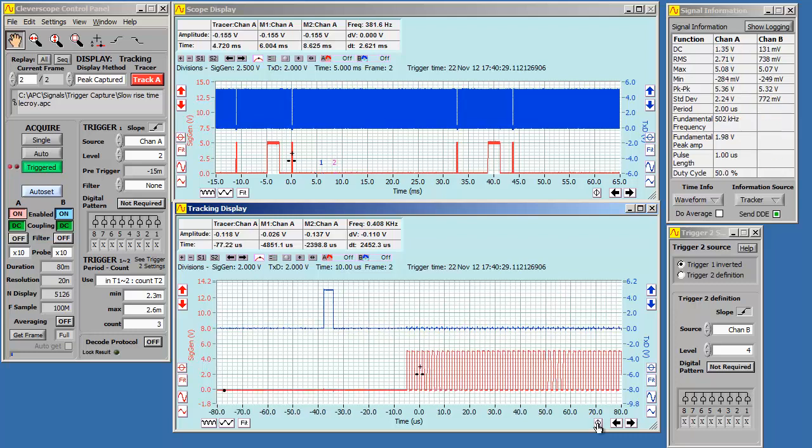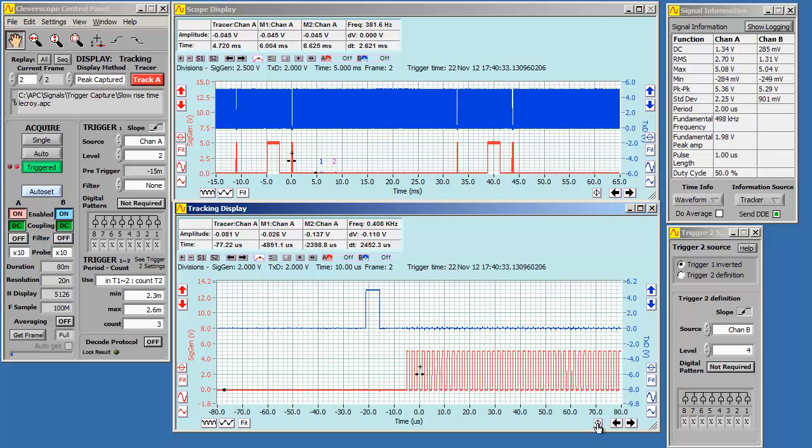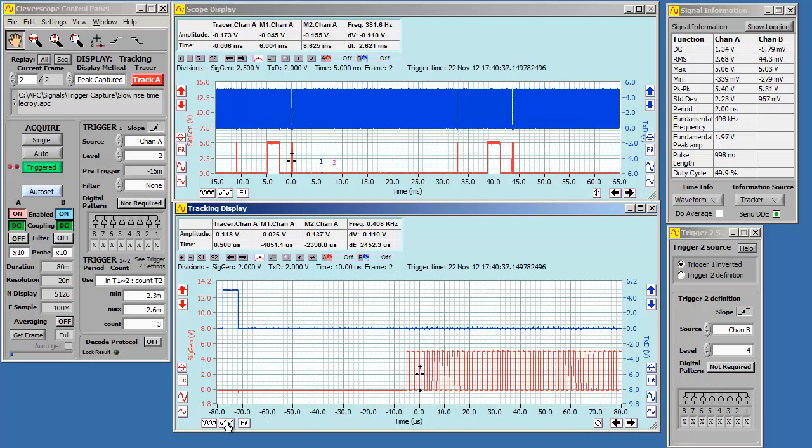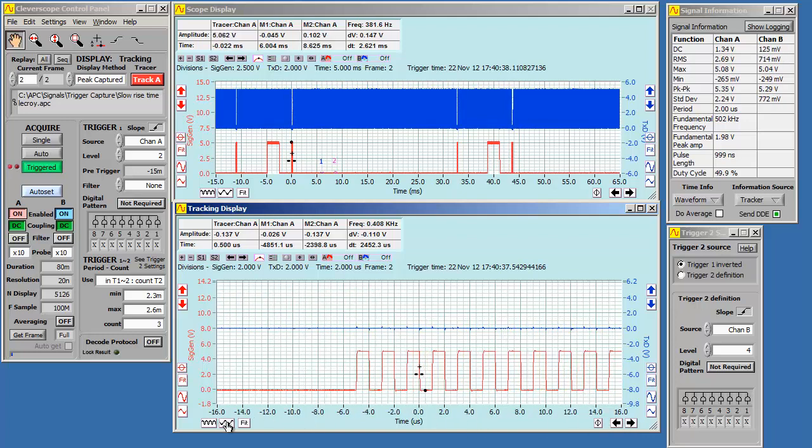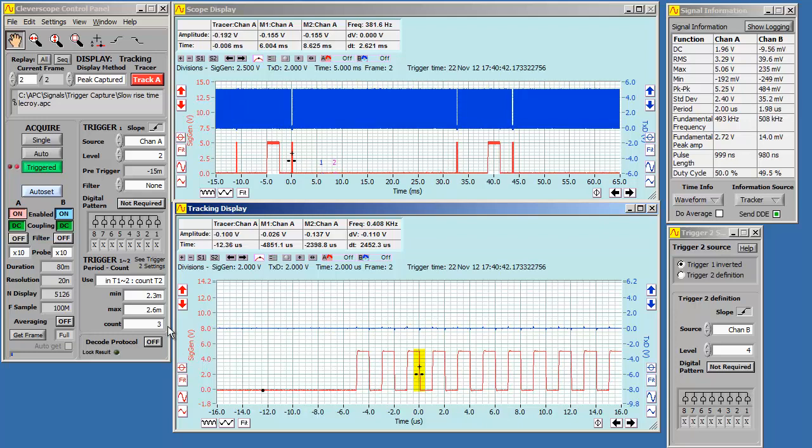We click on the 0 button to bring the trigger position into view. Now you can see we are triggering on the pulse burst. We zoom in, and you can see we are triggering on the third falling edge in the burst.